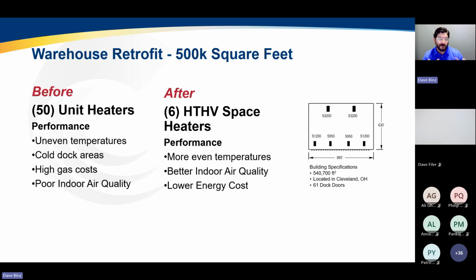It was installed previously with roughly 50 unit heaters, your traditional indirect fired, 80% efficient unit heaters. The building had no real mechanical ventilation. So with that, they had high stratification. They had very uneven temperatures from floor to ceiling and wall to wall. The building had really no pressurization, no mechanical ventilation. And so as you can imagine, dock areas were very cold and drafty as those dock doors opened and that infiltration came in untempered, untreated. The building could have been 65 degrees in the middle of the space, but they are feeling that harsh 0 degree, negative 10 degree air coming in that dock door. And so very uncomfortable conditions for their workers.